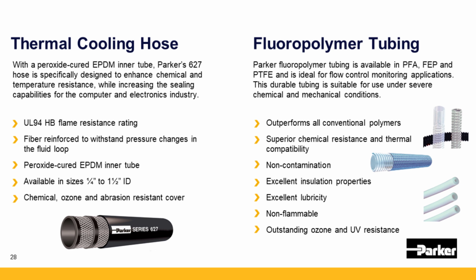Parker proposes EPDM hoses for water cooling applications in various internal diameters in order to answer the needs of connection in various places of the data center cooling system. They have high compatibility characteristics, an ozone and abrasion resistant cover, for example, for the Parker 627 series. For this series, the peroxide cured option offers even higher thermal resistance and compatibility. Some data center applications request a flame resistance rating, so Parker qualified some of the hoses following the UL specification.